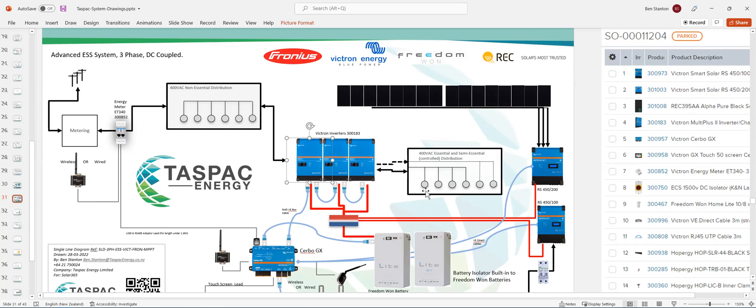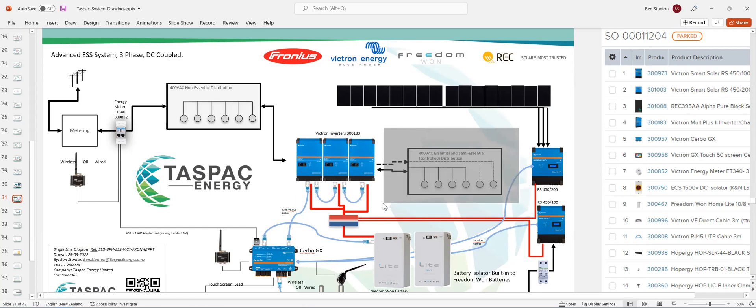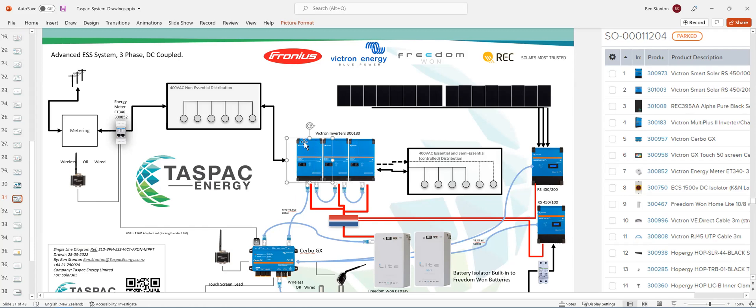Now, the key is if you've got parallel inverters on the same phase, you need to keep the AC and the DC cable lengths the same length. But because you haven't, you've got individual loads running off individual inverters, it doesn't matter. But try and spread the loads so you don't get more than five or six kilowatts of maximum demand expected per phase, per inverter. So the more you can spread those loads, the better it will be when the system goes into backup. You want all the inverters to be evenly loaded as much as possible.